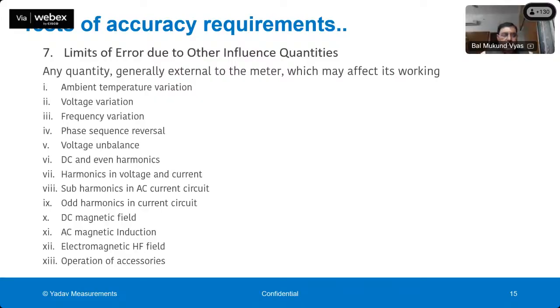But another important thing is that we have found that many people try to tamper with the meter or make it slow using very heavy magnetic fields. So in India, there is a requirement of testing electricity meters with fairly heavy magnetic fields, for example, 0.5 Tesla DC magnet or 10 millitesla AC magnet and so on. So such accuracy testing is there, and these meters have features to record tampering using magnets.